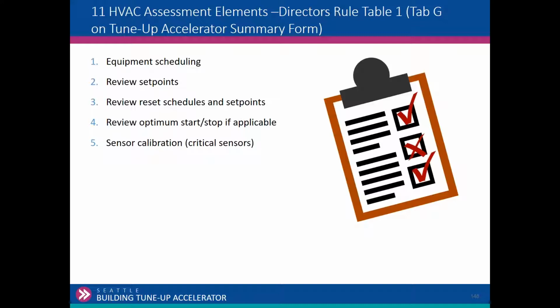Sensor calibration, and I emphasize critical sensors. Don't worry about room temperature sensors, but think about those sensors that initiate control action, system-wide control action. Functional testing, that is important. So for those 10 rooftop units, those 20 VAV air handlers, how do they function? Do the controls function correctly? On a rise in temperature, does the VAV damper open? On a drop in temperature, does the VAV damper close? On a drop in temperature, does it stay at minimum position and energize reheat? So just use your judgment in applying those sequences to that piece of equipment.